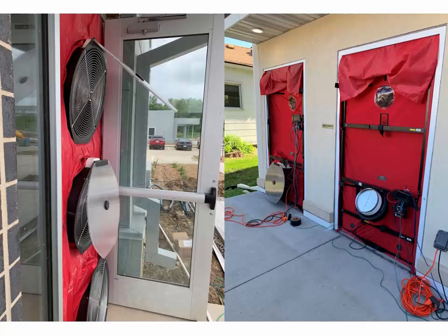You'll also notice on the right here, Energy Conservatory built us an automatic damper for the duct blaster fan as well. And this one was actually quite interesting. It's a 10-inch butterfly damper mounted directly to the fan. And this one was actually calibrated and tested as accurate down to 50 CFM. So we were actually using this for our compartmentalization and unit exterior leakage measurements.